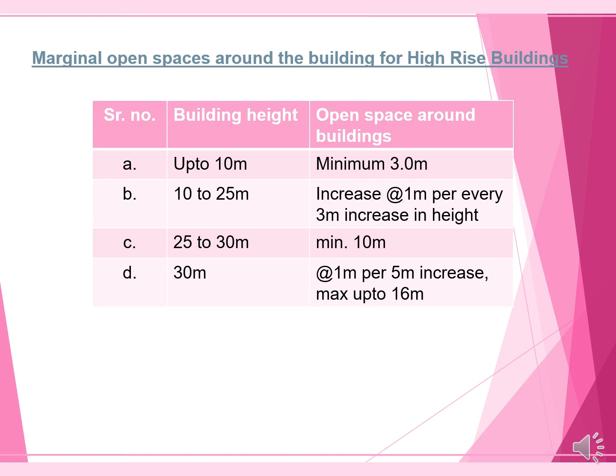Firefighting provision to be incorporated in high-rise buildings of more than 24 meter height. Maximum travel distance from the farthest exit on a floor to the staircase is 22.5 meter, and 30 meter in case of commercial buildings. Provision of a fire lift is mandatory for buildings of height more than 24 meter. Fire equipment as per IS code.